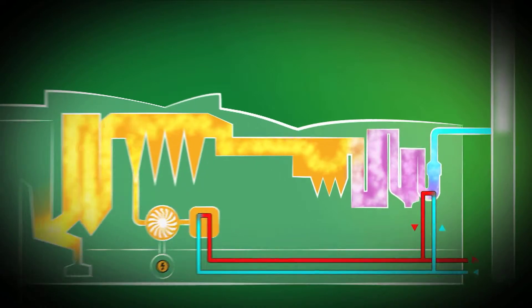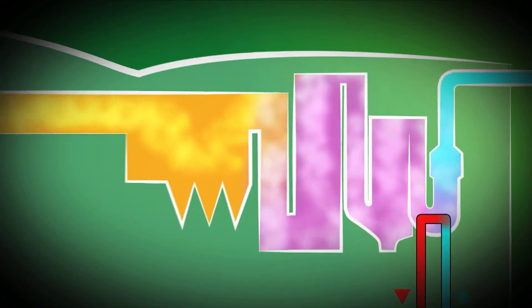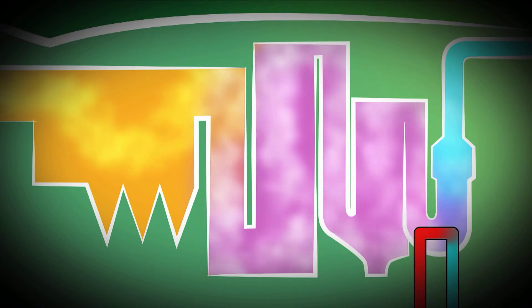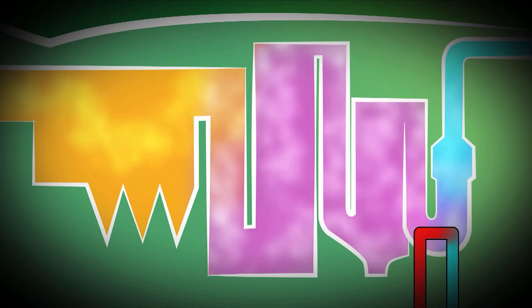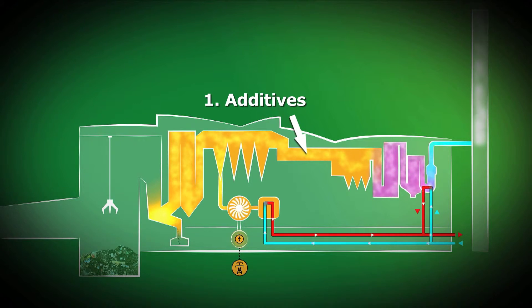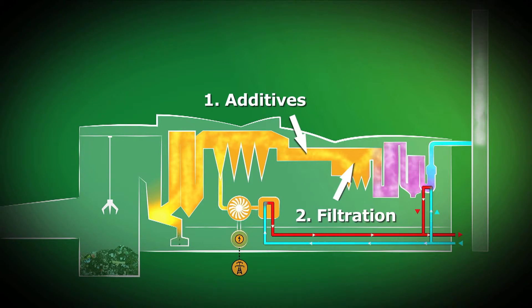The purpose of the flue gas cleaning is to transform the environmentally hazardous substances to a solid material, which is easier to remove and handle. Activated carbon and lime are added to the flue gas and react with acidic substances and heavy metals to form particles. The flue gas goes through a bag house filter where particles are filtered out and disposed of as hazardous waste.